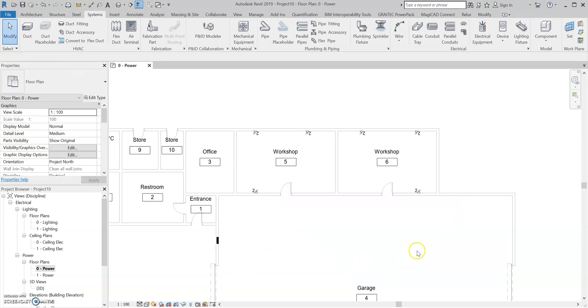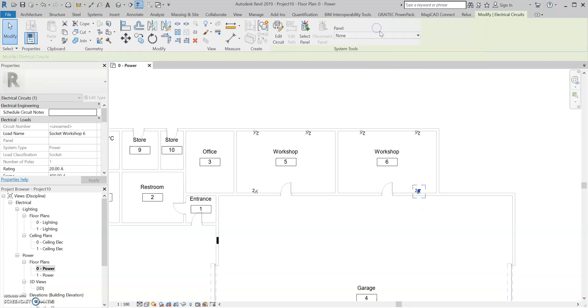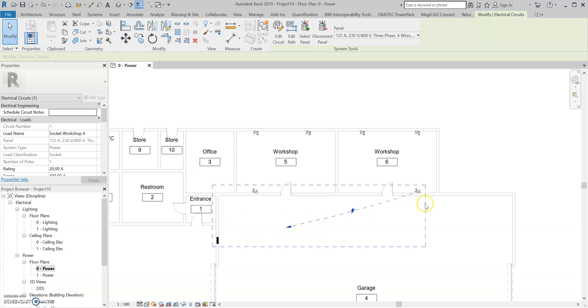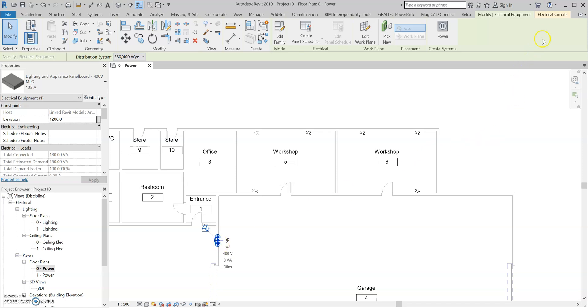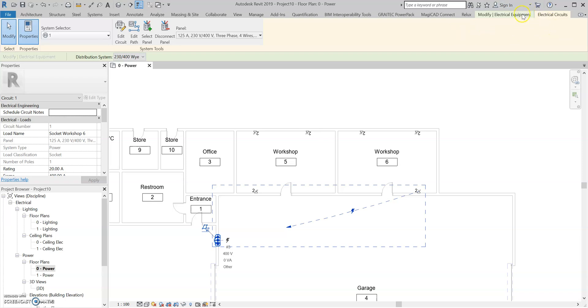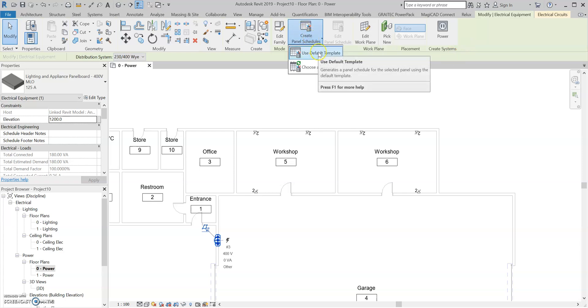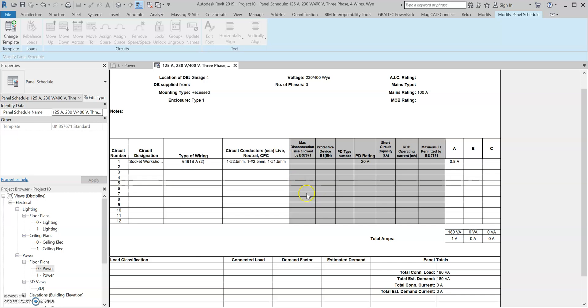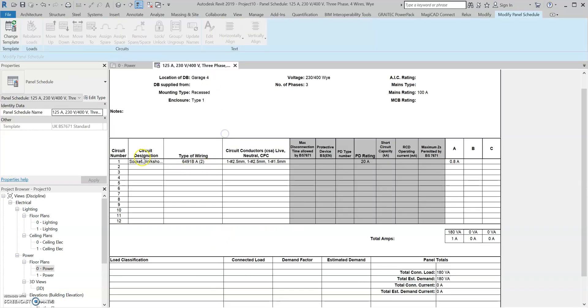So now we can start adding power to our sockets. I'm going to select the socket, select Power, and from the panel board drop-down, select the panel board. This socket is now circuited to it. You'll know a circuit is created when you select the panel board and go over to Modify Electrical Equipment and create a new panel schedule — I'm going to use the default. You'll notice that the socket circuited to this panel board is now showing in the schedule.